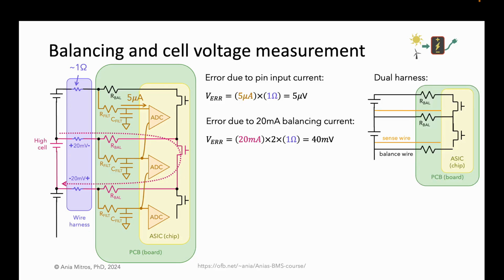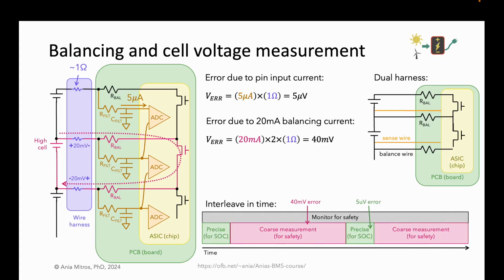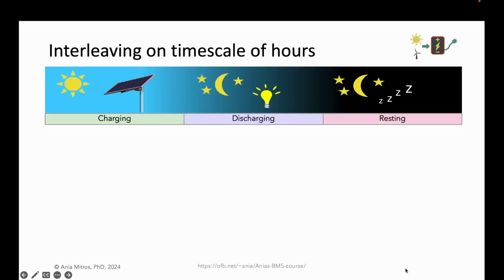One solution is a duplicate harness with 2 wires to each cell, one for balancing and the second for sensing. Cost and mechanical complexity are often prohibitive for the dual harness solution. Another solution is to interleave balancing and precision cell voltage measurements. During balancing, the system takes coarse cell voltage measurements, sufficient for safety monitoring. On what timescale do we do this interleaving? One possibility is to do it on a timescale of hours.